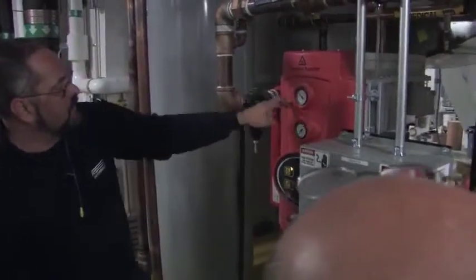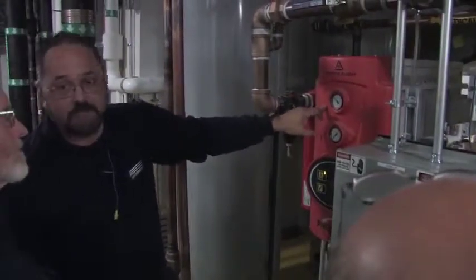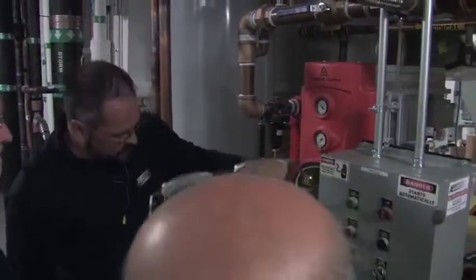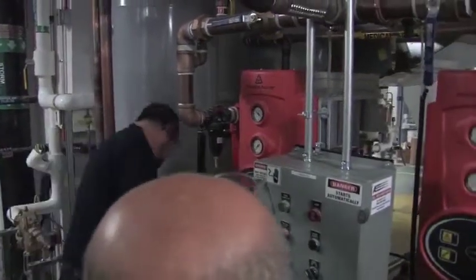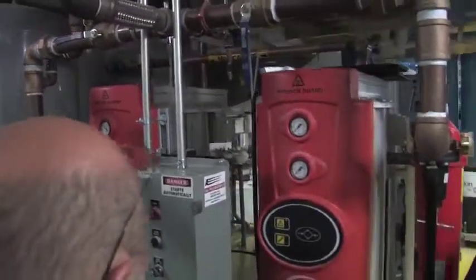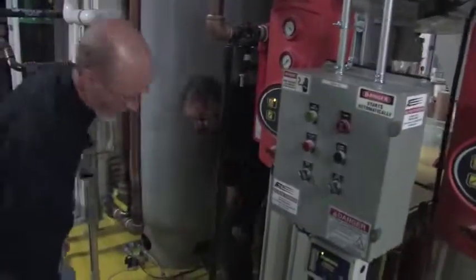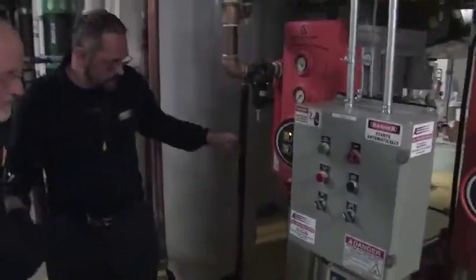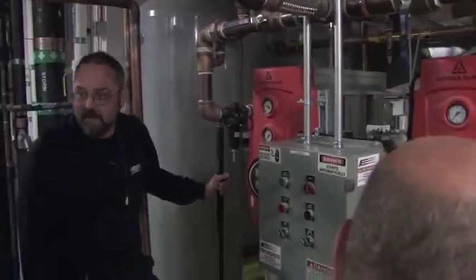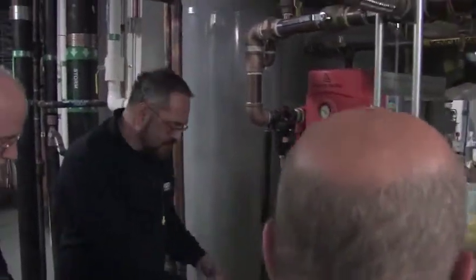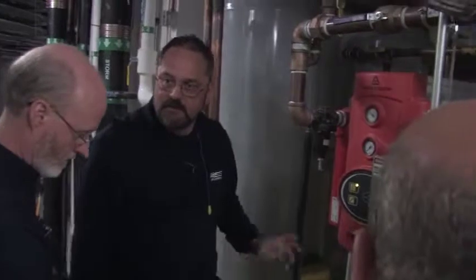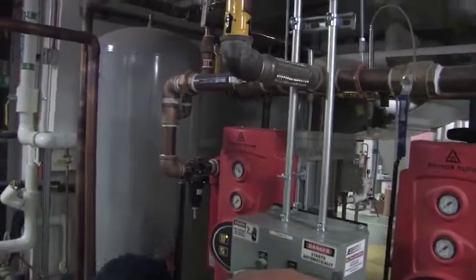Okay, right now, left tower's on. Right tower's purging. If we go down and feel the muffler underneath, you'll feel damp air coming out of that muffler. Now, damp air, and it maybe condenses and makes a little moisture right there, is okay. If you see liquid water pouring out of there, very bad. Time to look at the pre-filter, figure out where the water's coming from.